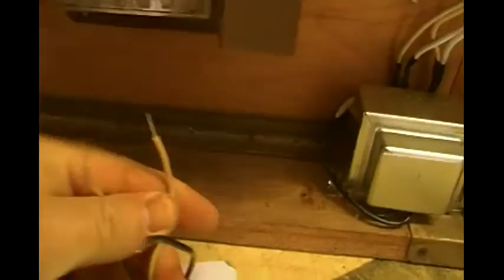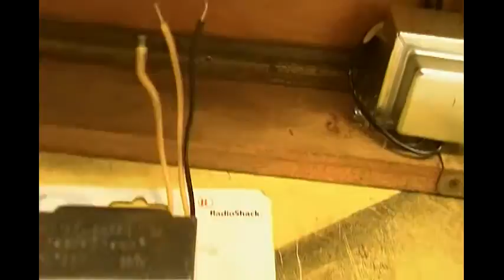So as you can see here on the output side, there are 2 yellow wires and 1 center tap black wire. The 2 yellow wires will be the 24 volts to run the solenoids. The black wire and either one of the yellow wires, it doesn't matter which one, will give you half the voltage, the 12 volts, which will run the lights.